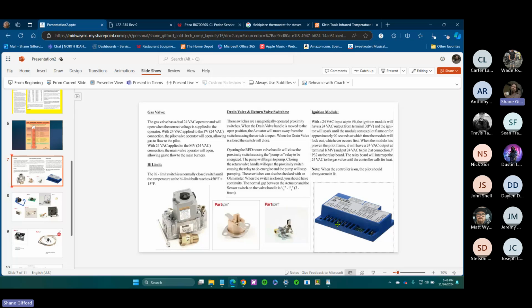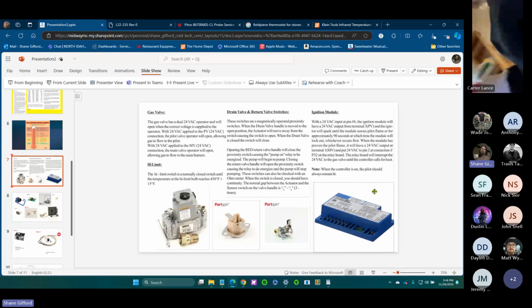Ignition module. I know everybody's seen one of these. Honeywell makes one. It's a little black one. You can put it on just about anything. So if you do have a failed ignition module, chances are you can get the aftermarket one from Johnstone Supply. This will run fryers. It'll run the Modine and Reznor space heaters. In fact, Captive Aire has a version of their own. I think it's called a Maxitrol. It's linked with the gas valve, but essentially it's got main valve, pilot valve, 24 volts, spark, all this stuff, your W circuit. And this is the control board for whatever hot appliance you're working on.